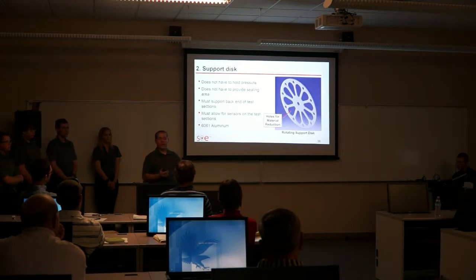The second component is the support disc. This disc does not have to hold pressure, which allows us to cut additional holes into it to make it lighter. This disc does not have to provide sealing, which allows us to make it overall smaller, giving us an overall diameter of 34 inches instead of 36.